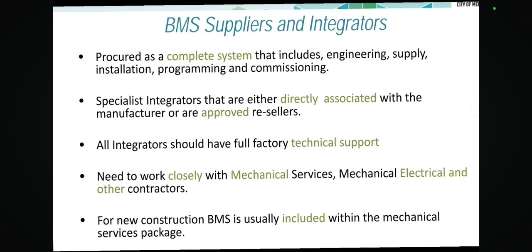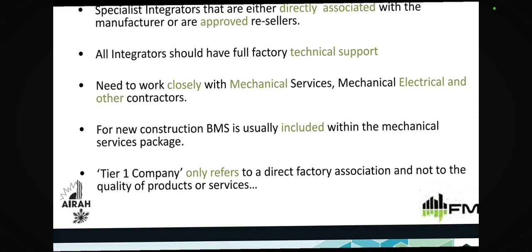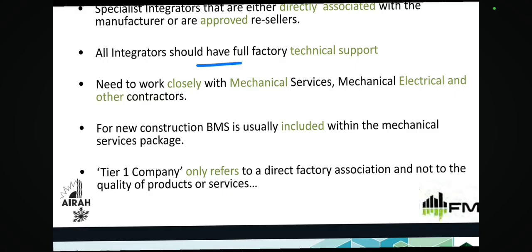BMS supply and integration. Procured as a complete system that includes engineering, supply, installation, programming, and commissioning. Specialist integrators are either directly associated with the manufacturer or are approved resellers, and all integrators should have full factory technical support. They need to work closely with mechanical, electrical, and other contractors. For new construction, BMS is usually included within the mechanical service package.